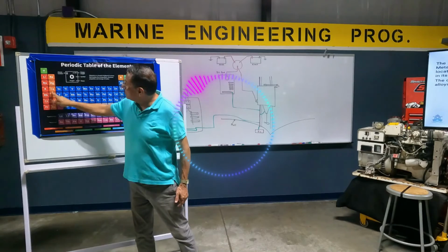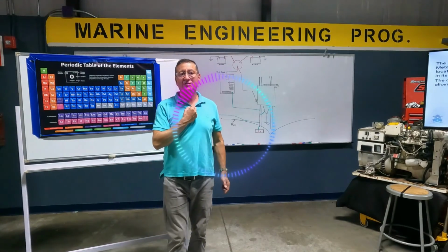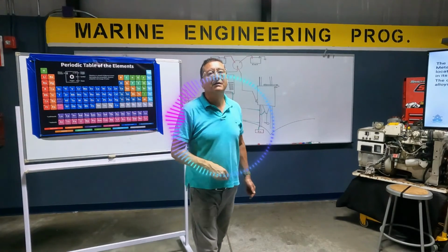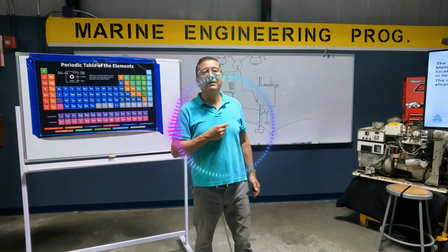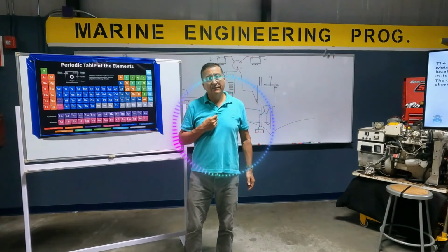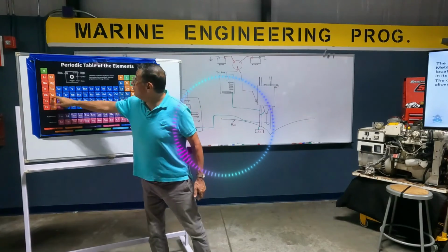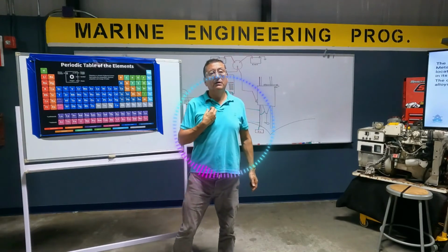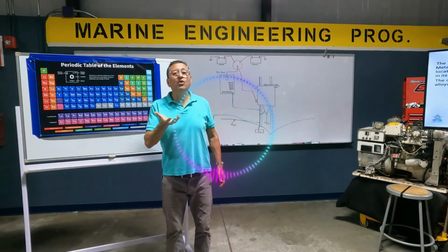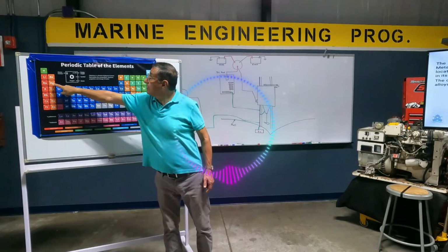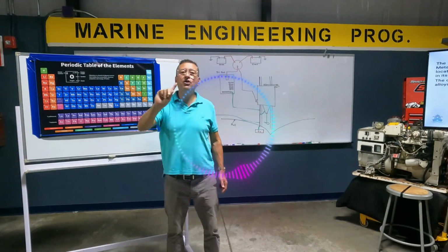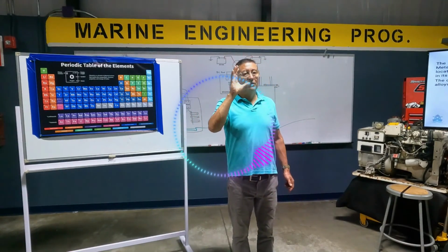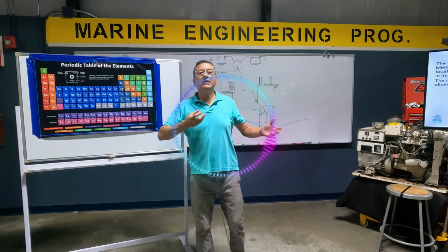This is catastrophic. For that reason, if the reverse polarity indicator light is on, you need to solve the problem immediately. If not, probably your bonding bus bar right now is powered with AC power, 120 or 240. Be careful with that. This is the procedure to do the wiring in AC power. I think that is simple. You need to be careful, use the appropriate tools, and use goggles. Be careful with the AC current. The AC current is critical.